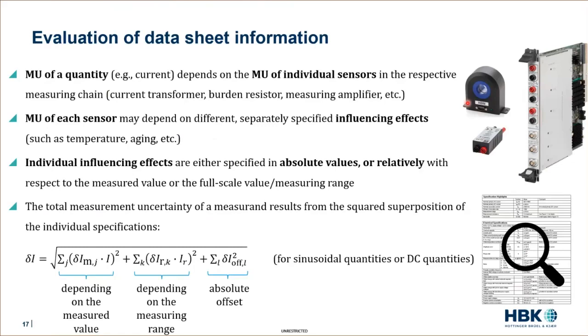So what we should do is calculate the measurement uncertainty of all those components. Each component, if you look into the data sheets, is specified with different influencing effects, such as temperature dependent errors, aging dependent errors, nonlinearity error, or Earth's magnetic field influence, and all those things.